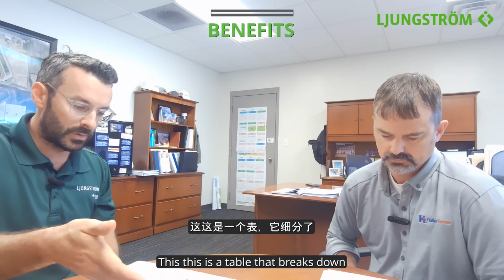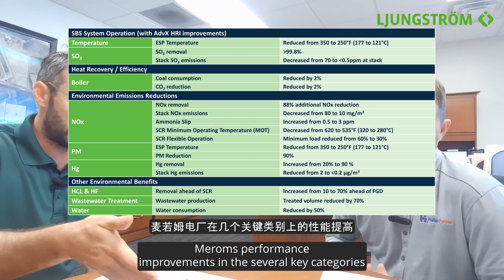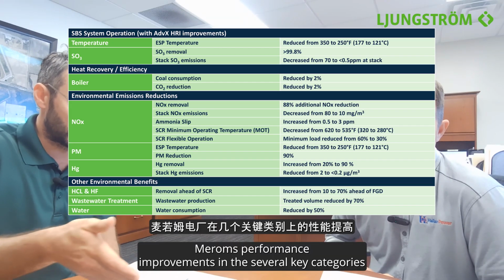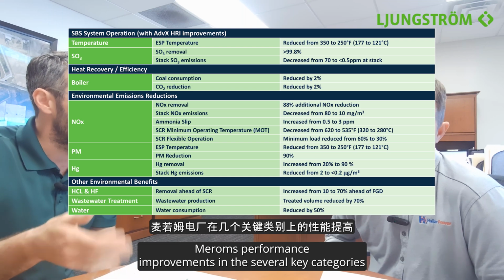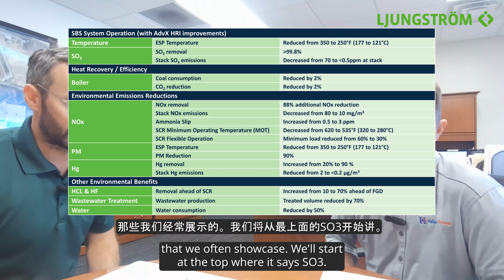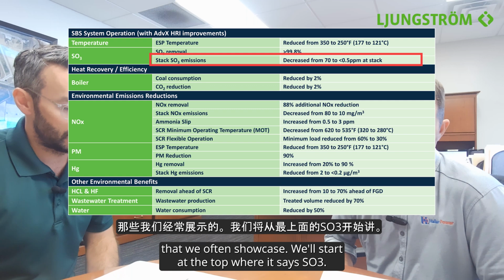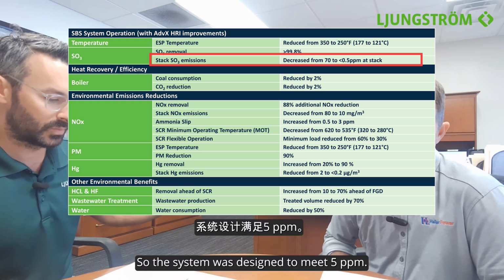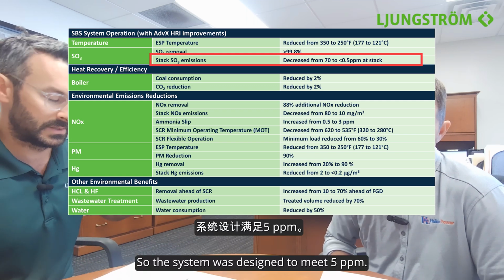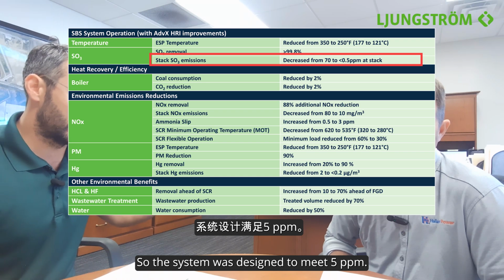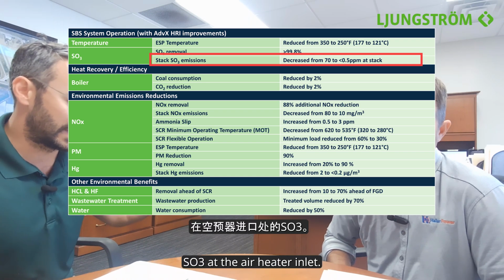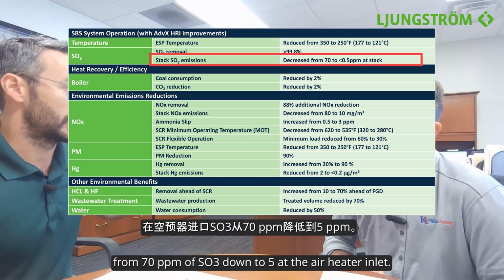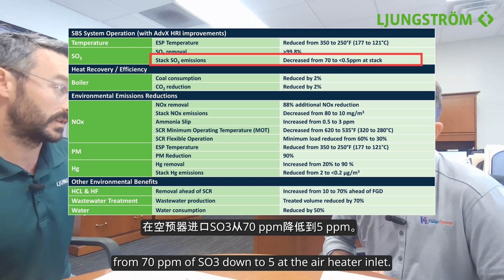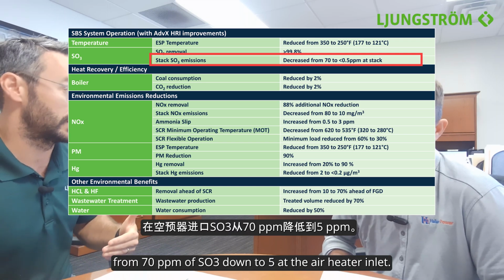This is a table that breaks down Merom's performance improvements in several key categories that we often showcase. We'll start at the top where it says SO3. So the system was designed to meet 5 ppm or less SO3 at the air heater inlet, from 70 ppm of SO3 down to 5 at the air heater inlet.